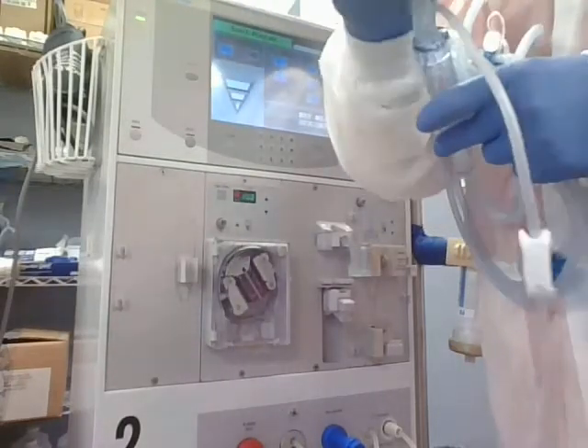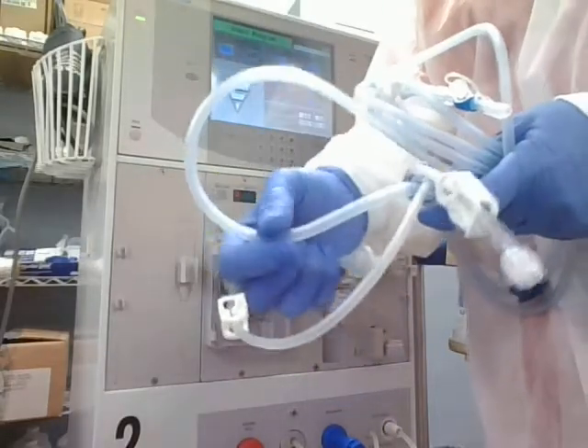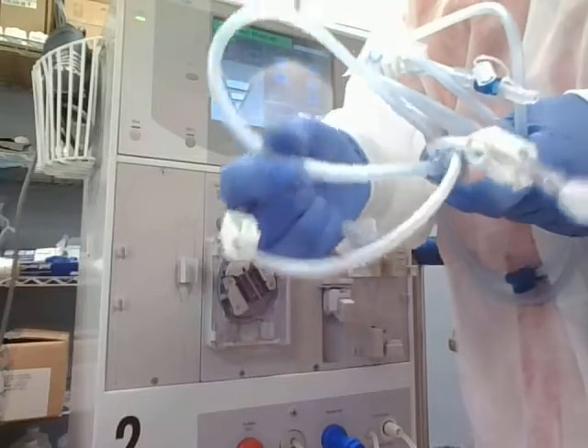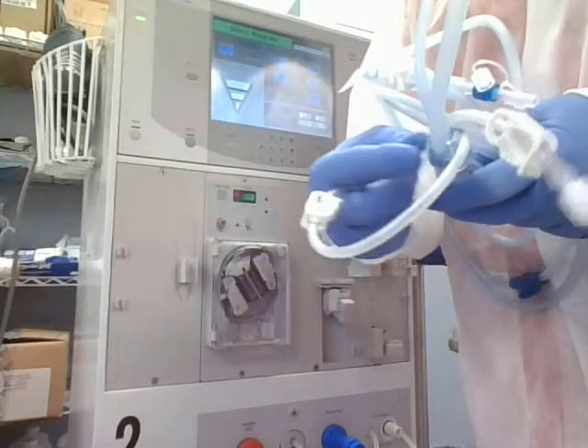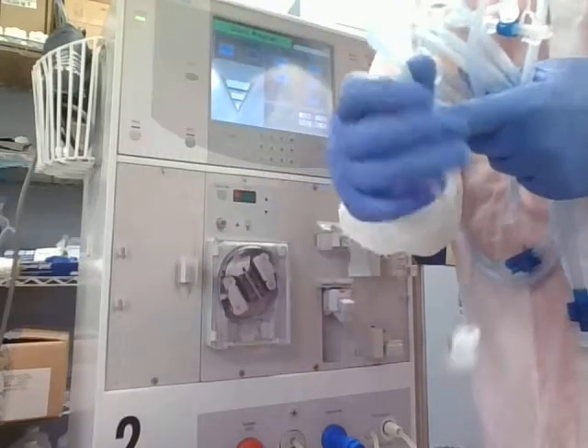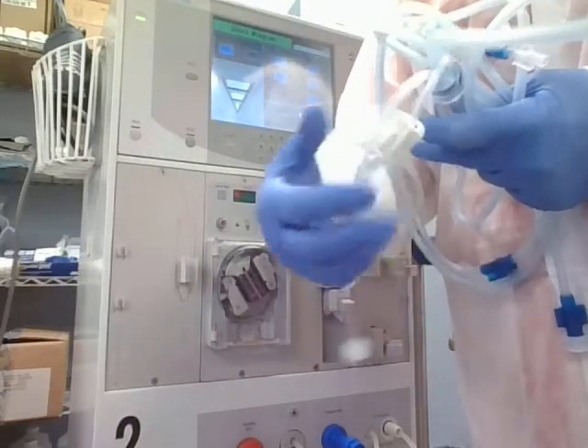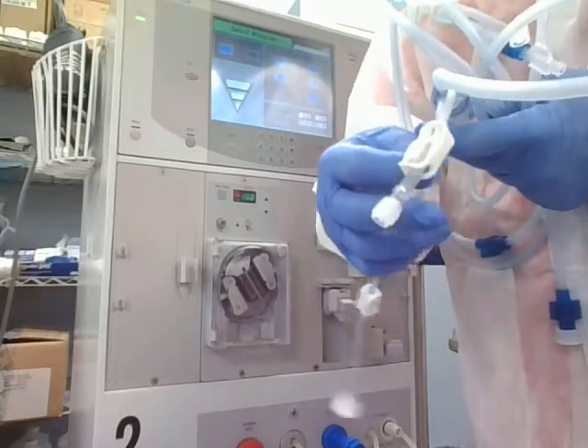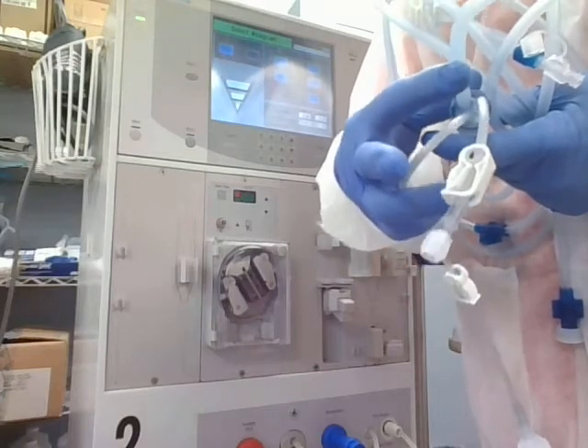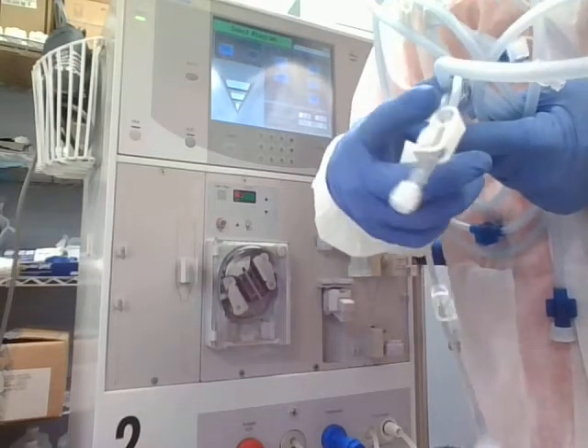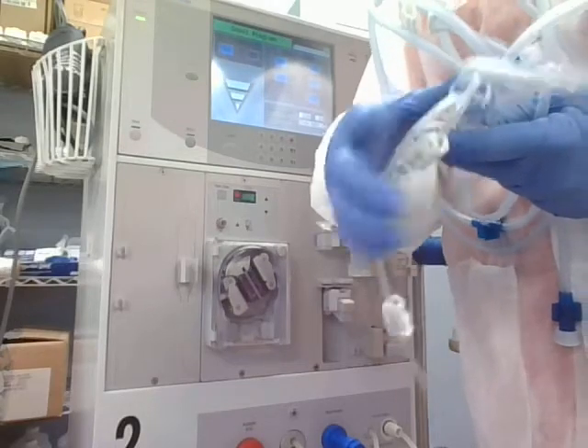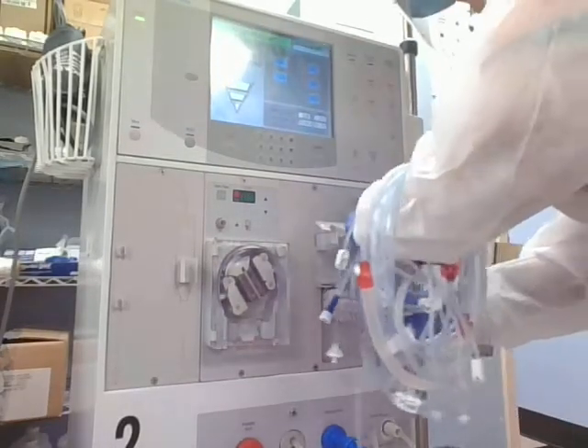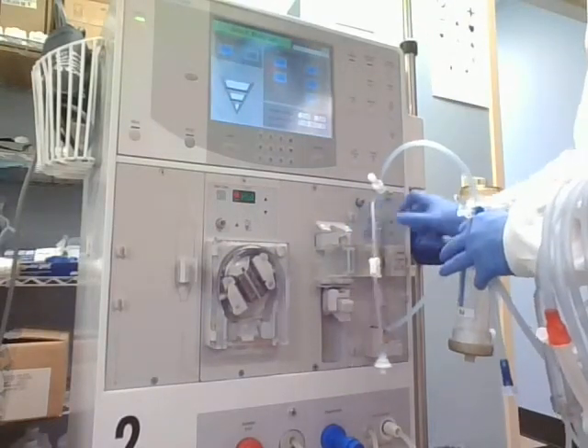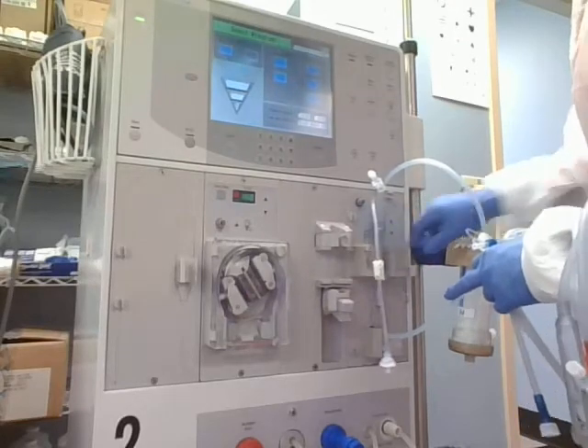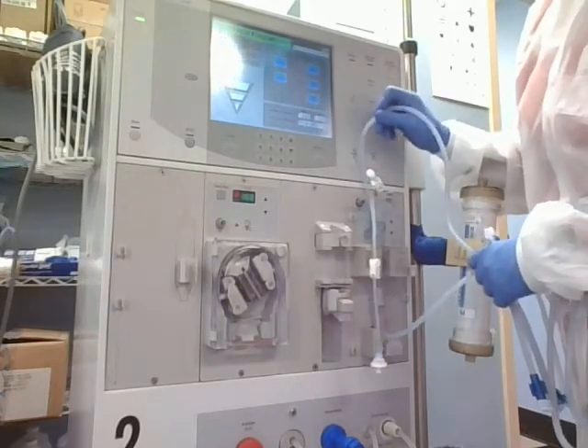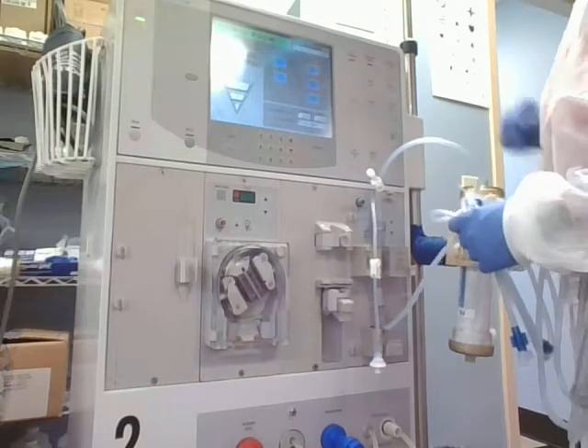The third line that's coming in, this is your blood line. This is actually coming in from your patient, or in the case of priming, it's going to be coming from your saline. So I call this one the fat boy. If you look at the other two, these two are really skinny. So I call him the fat boy just to get the point across that the thicker blood tubing is the one that you want to the back. So the little catchphrase that we say here in this lab is fat boy to the back. So you're going to take your lines and place your drip chamber into the air foam detector and close the door, making sure that your blood line, or your fat boy, is to the back towards the machine.